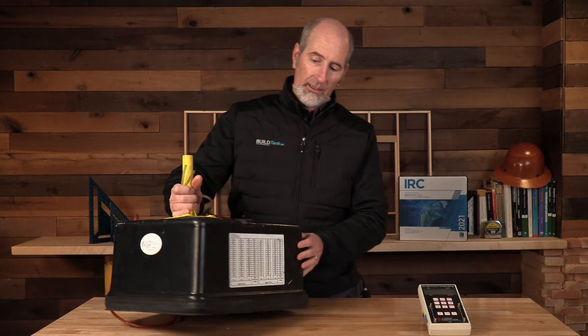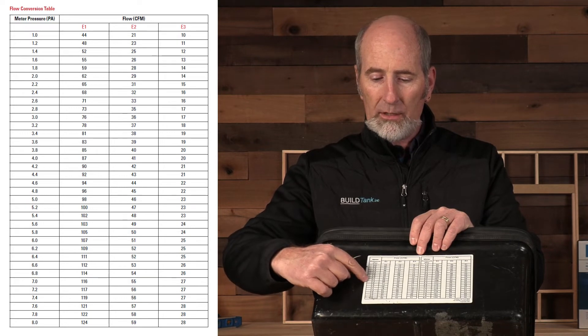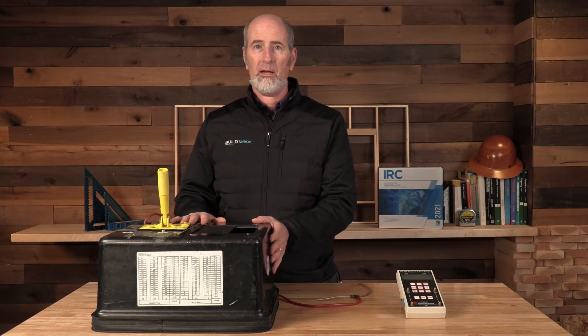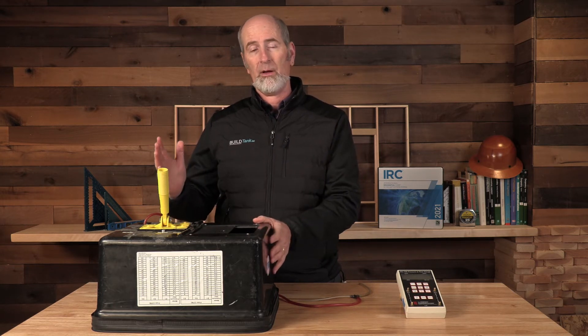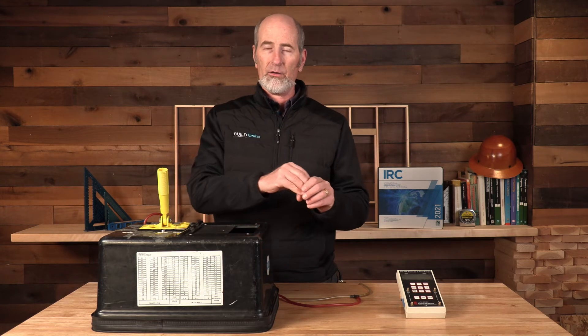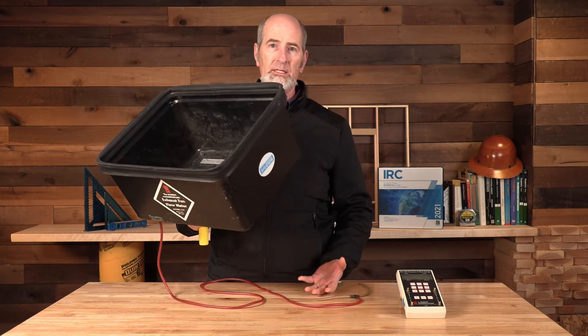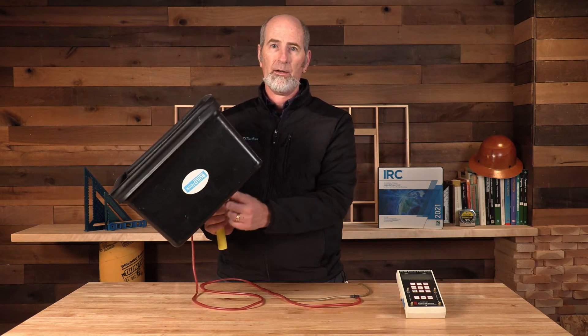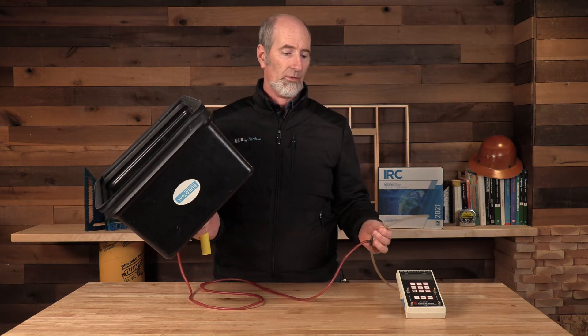On the other side of the hose, there is a Y-fitting so I can hook up to both sides of my gauge to measure pressure, and then the gauge can translate that pressure measurement into a flow measurement. Alternatively, I can use the handy guide and just measure the pressure inside the box relative to outside — if I know the opening size and the pressure, I can look across the table and get the flow measurement. Air flows when we have two things: a hole and a pressure difference or driving force. In an exhaust fan, we create negative pressure — air being sucked out of the room. When I place this over the fan and create a tight seal, air is sucked into the flow box through the known opening, creating a measurable pressure difference.